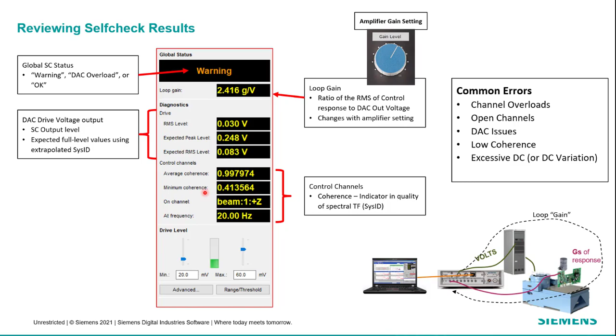Yeah, Charles, when I look at the self-check results, I'm noticing one thing. I haven't used the vibration testing software as much as you have, certainly, but I noticed the minimum level seems a little bit higher than I normally use when I just turn on the software, the default value. Is that kind of a recommended value? This, yeah, this down here. So, out of the box, the test lab software is always going to be very, very conservative. I think the minimum default value is 5 millivolts.